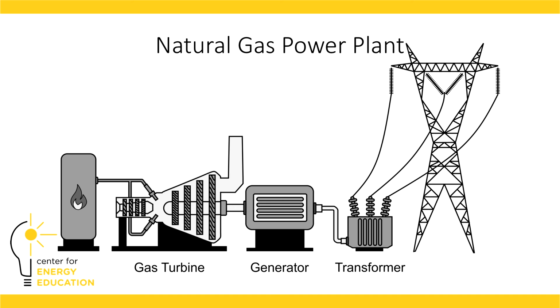Here we have the basic building blocks of an open-cycle natural gas power plant. We don't see a boiler feeding a steam turbine, but instead we see natural gas being fed to a gas turbine. Other than that, we have the same components found in a coal-fired power plant. The gas turbine is connected to a generator whose output feeds a transformer, sending voltage to the power grid.